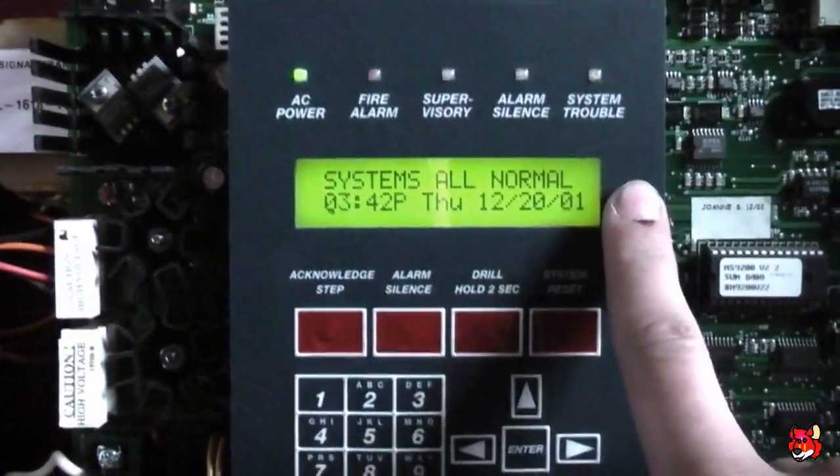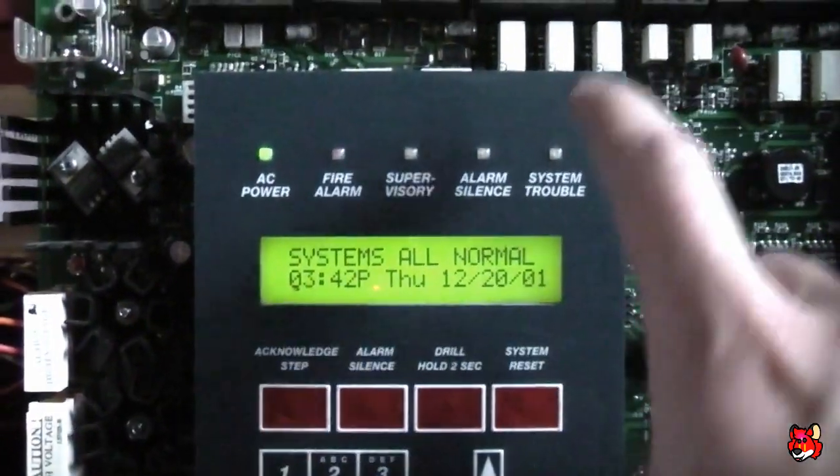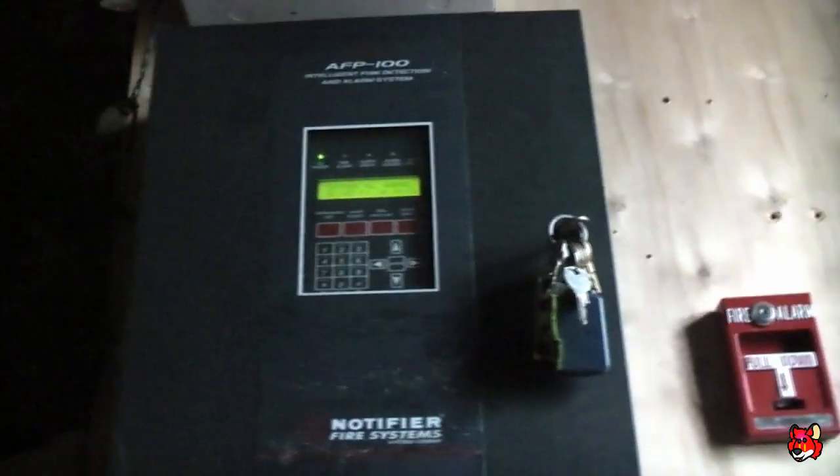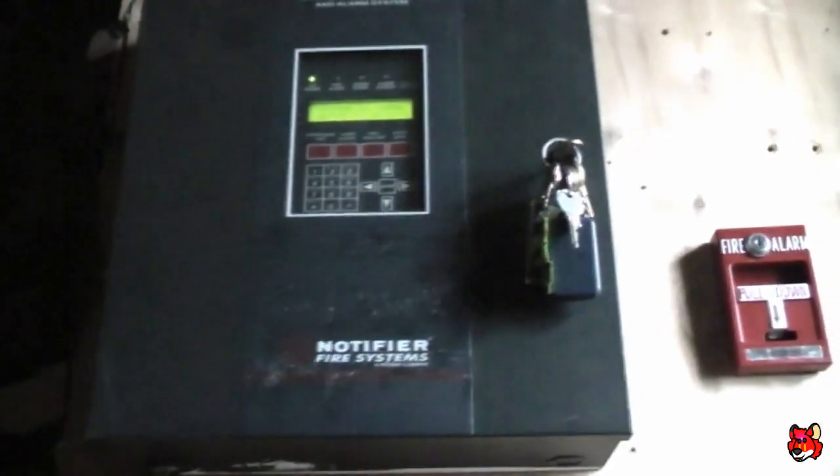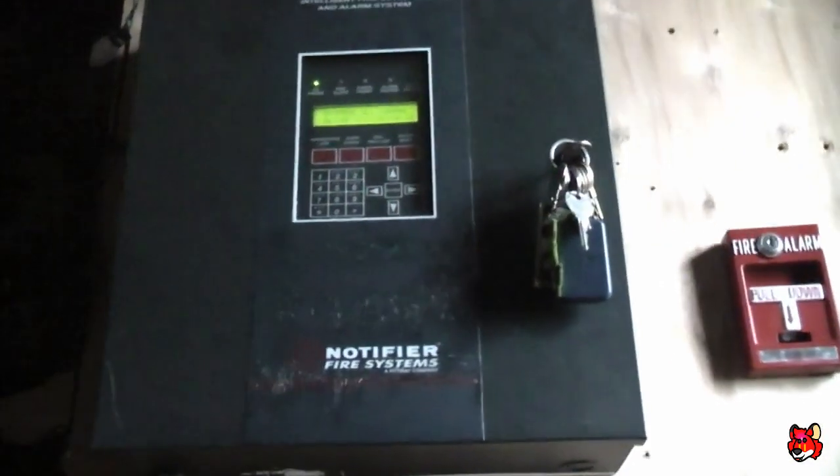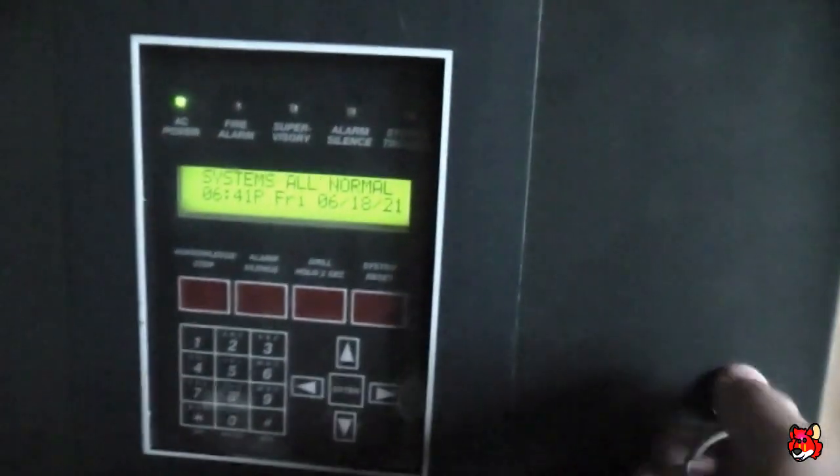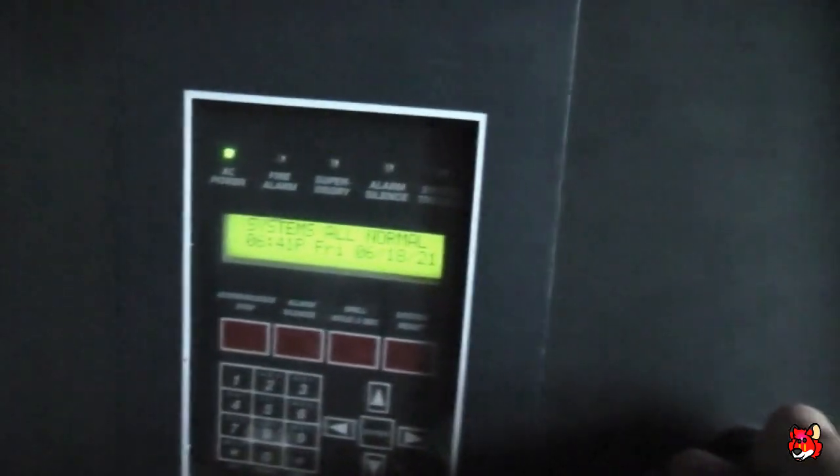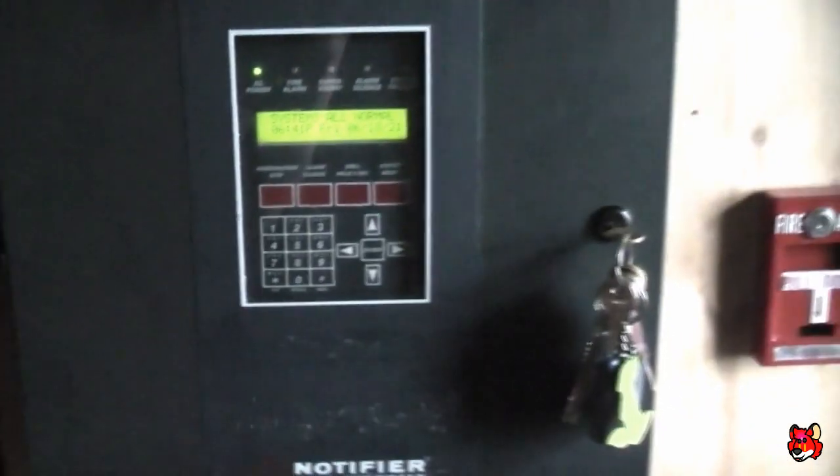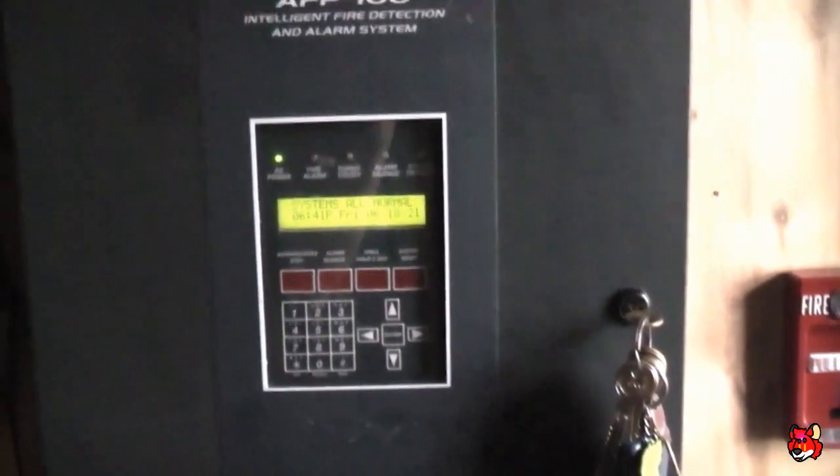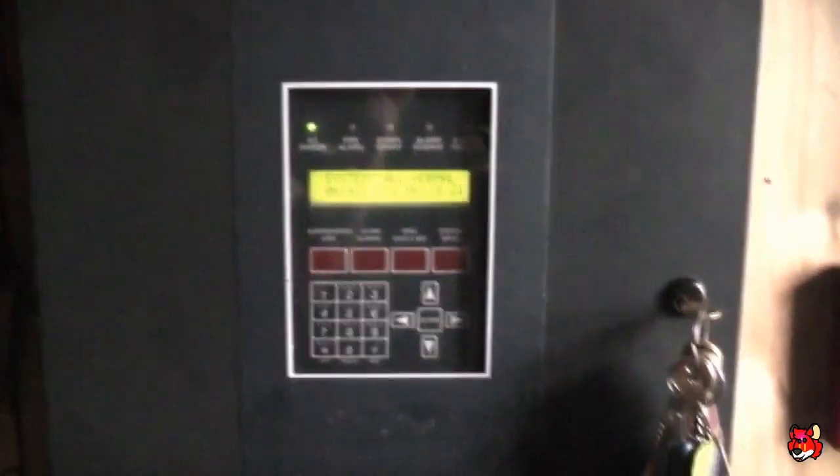And there are other differences between this and the Notifier panel. For starters, this one, the AFP100, it may be a rebranded MS9200. It even says that right there. But this panel cannot take Firelight devices. And I have already tried that before. I tried hooking up a few of my BG-12LX to it, my Firelight and my ADT. The panel would not take them.